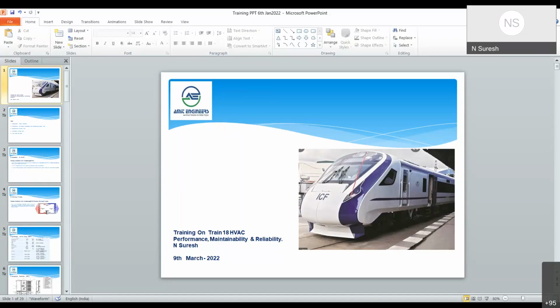To achieve this, what is the process? Cooling, dehumidification, heating, and air filtration. Cooling is to reduce the temperature from the initial temperature. That's where the refrigeration system works. Dehumidification, again, the refrigeration system dehumidifies by the evaporation process. Heating is used for winter application. And above all, air filtration is very important.